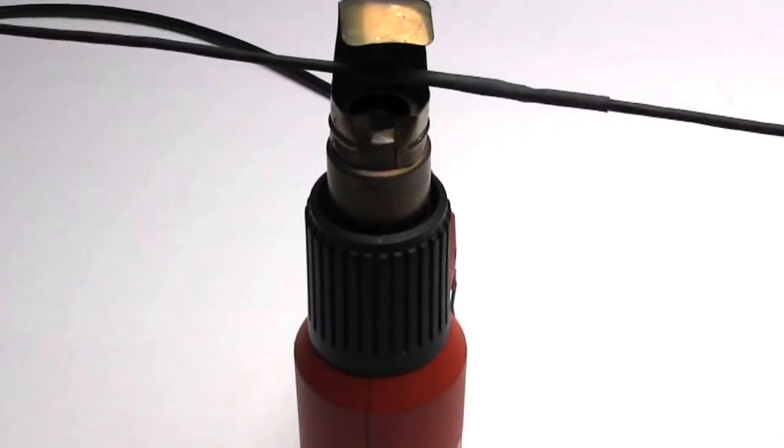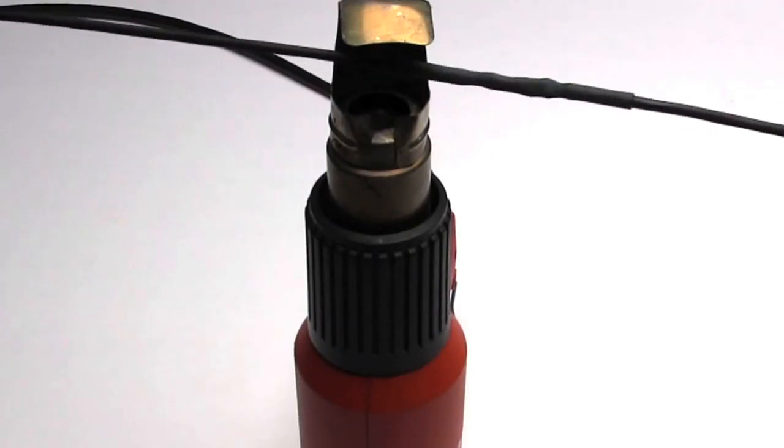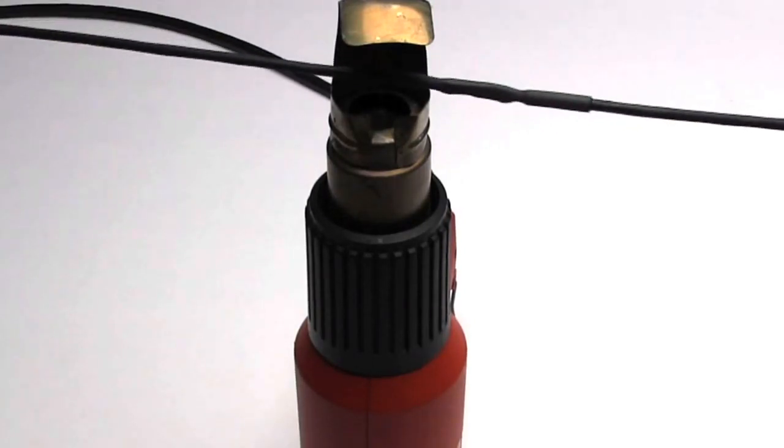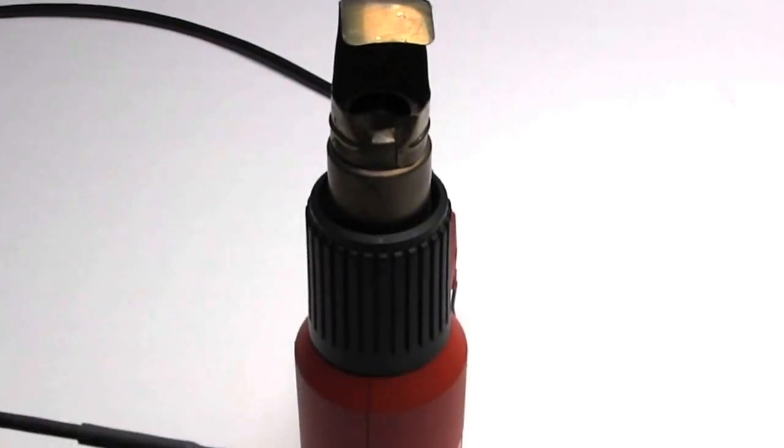Use the heat gun and notice the heat shrink forming tightly to the cable and splice. The adhesive lined heat shrink will have a glossy look once the glue is flowed. Be careful not to overheat the heat shrink. If overheated, it will start to warp and eventually melt away. Allow all the parts to cool before moving.